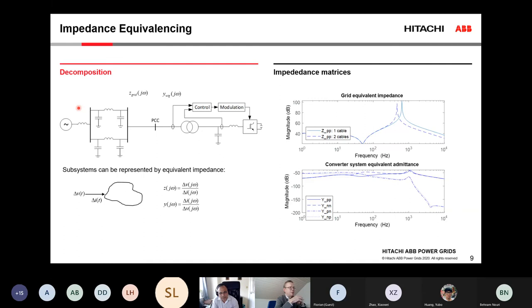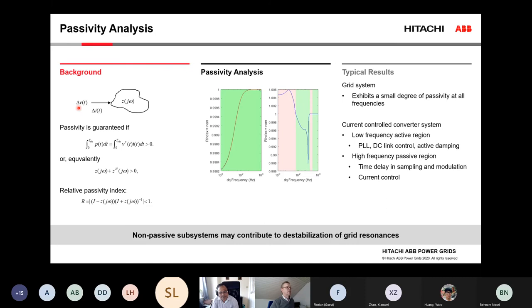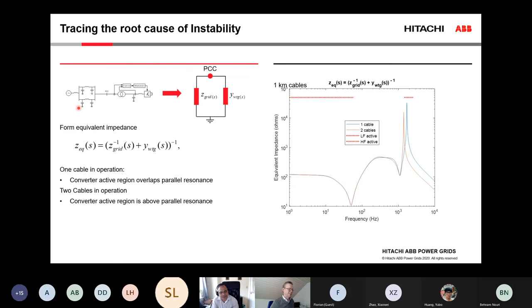And when you do modal analysis, we get damping, as each resonance mode gets a damping. And that damping is a very good indicator of what your steady state harmonic amplification will be. THD values. At least the amplification you can get from the damping. And once you know the injection as well, you can get the THD.